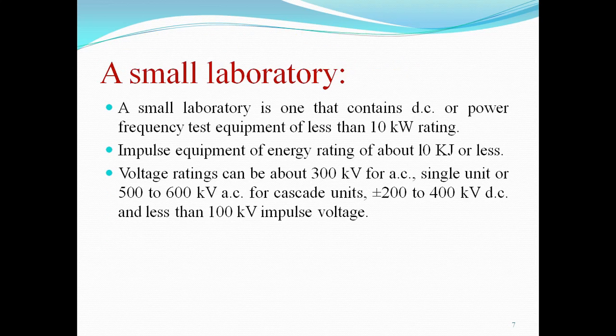So what is the meaning of a small laboratory? A small laboratory is one that contains DC or power frequency test equipment of less than 10 kilowatt rating, and impulse equipment of energy rating of about 10 kilojoule or less. Voltage ratings can be about 300 kV for AC single unit or 500 to 600 kV AC for cascade units, and plus minus 200 to 400 kV DC and less than 100 kV impulse voltage.